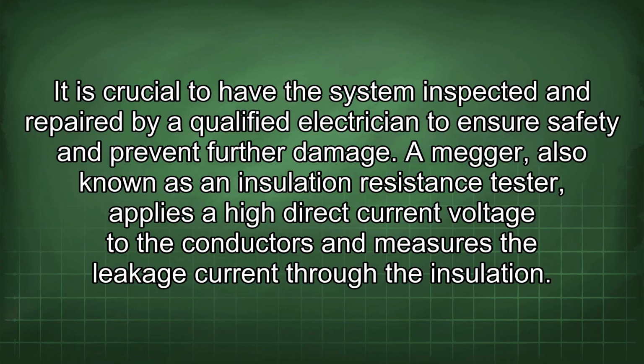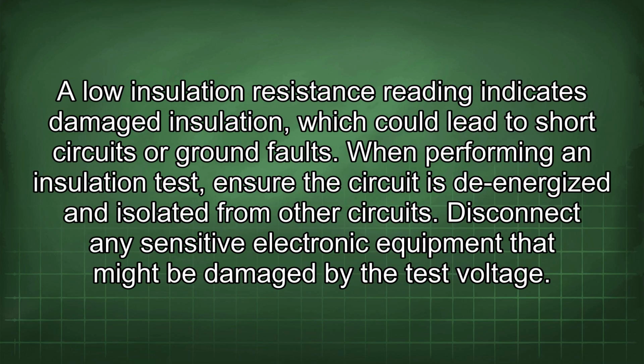A megger, also known as an insulation resistance tester, applies a high direct current voltage to the conductors and measures the leakage current through the insulation. A low insulation resistance reading indicates damaged insulation, which could lead to short circuits or ground faults. When performing an insulation test, ensure the circuit is de-energized and isolated from other circuits. Disconnect any sensitive electronic equipment that might be damaged by the test voltage.